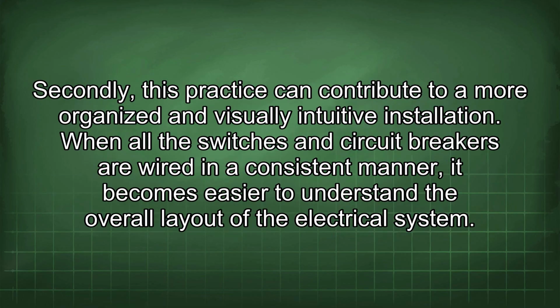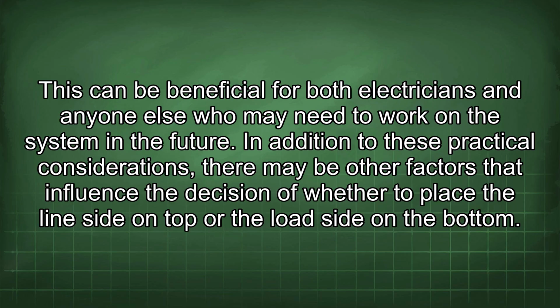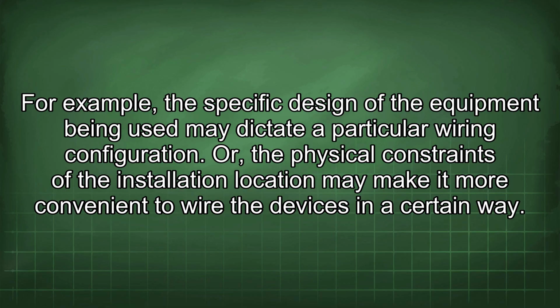Secondly, this practice can contribute to a more organized and visually intuitive installation. When all the switches and circuit breakers are wired in a consistent manner, it becomes easier to understand the overall layout of the electrical system. This can be beneficial for both electricians and anyone else who may need to work on the system in the future. In addition to these practical considerations, there may be other factors that influence the decision of whether to place the line side on top or the load side in the bottom. For example, the specific design of the equipment being used may dictate a particular wiring configuration, or the physical constraints of the installation location may make it more convenient to wire the devices in a certain way.